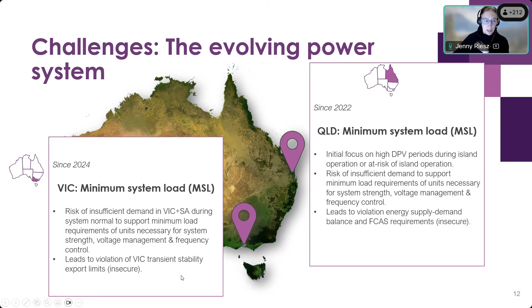Now, of course, in planning timeframes, there's a lot of potential to deliver those system services from alternatives. So there's a lot of looking at other alternative sources of system strength and voltage management, such as synchronous condensers, batteries for frequency control, and all sorts of other sources. But those are not available in the operational timeframes that we're looking at. So we're really limited to managing the system with what we have now. And we do foresee periods where that's becoming challenging. And the main risk that will emerge here is that if there's not enough load, then we will be violating interconnector limits, and particularly some transient stability export limits from Victoria that we have to manage very carefully.